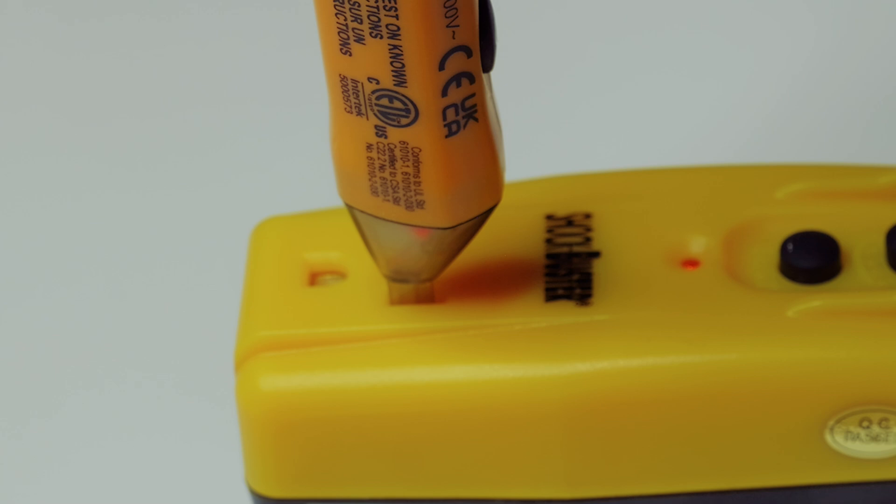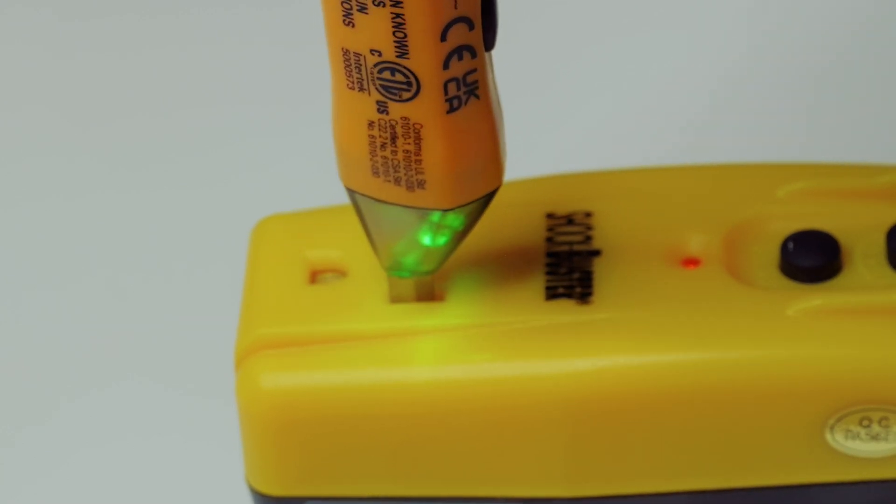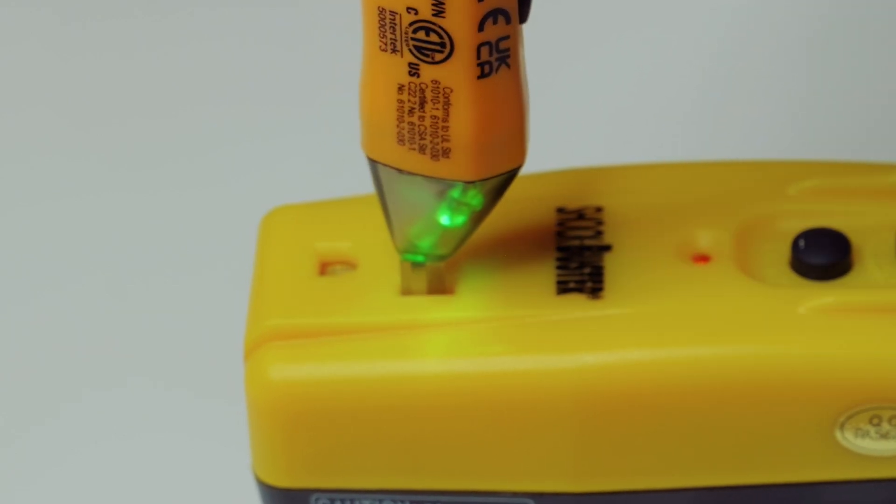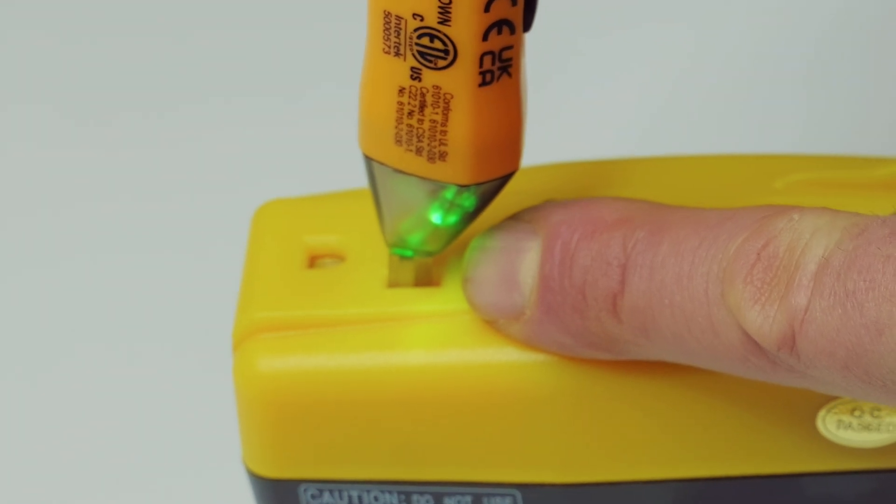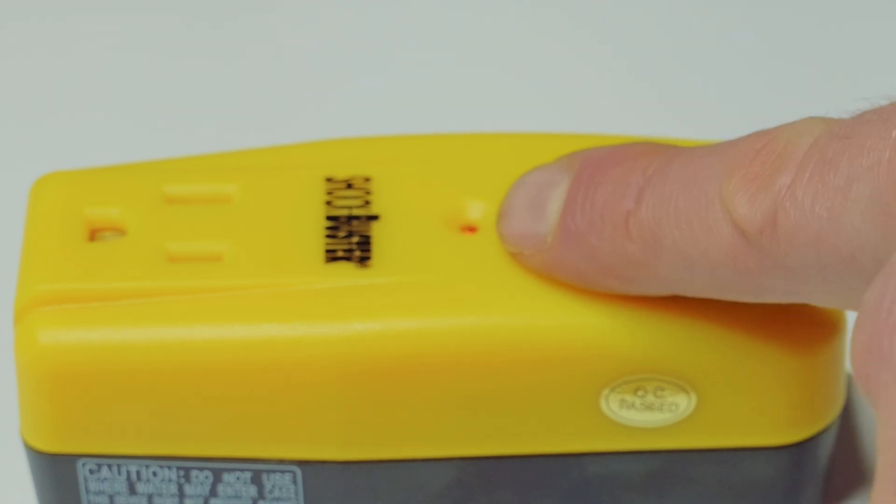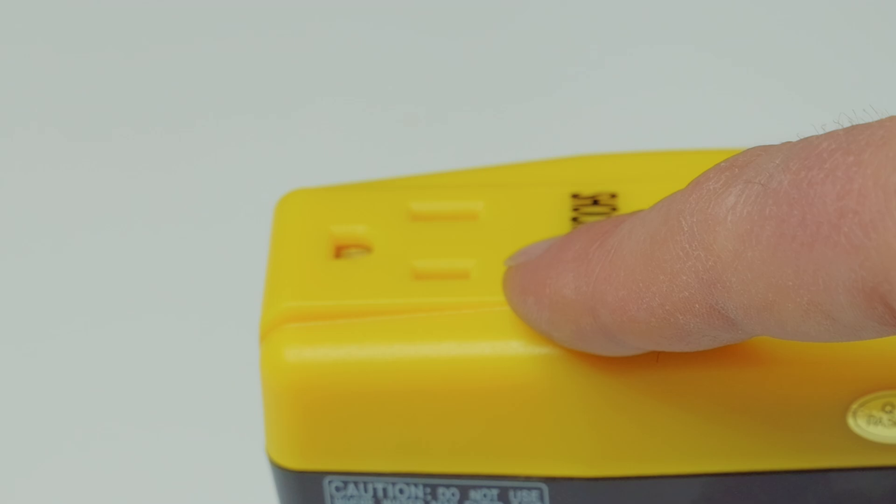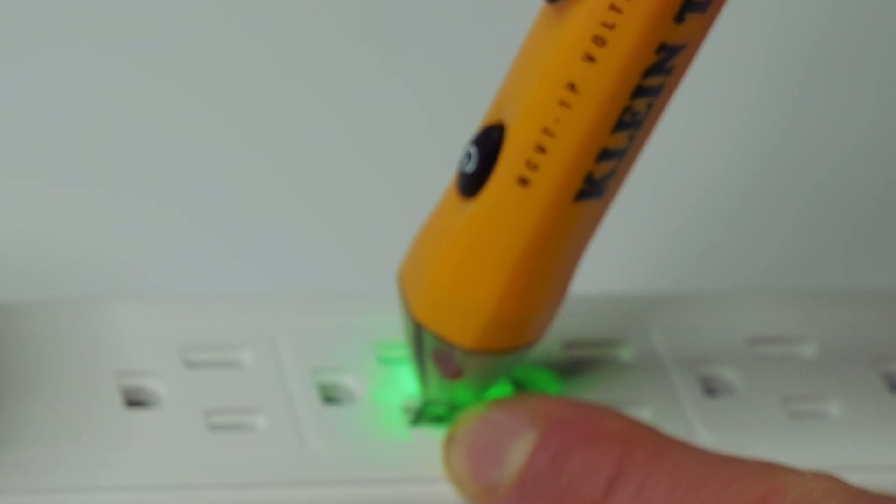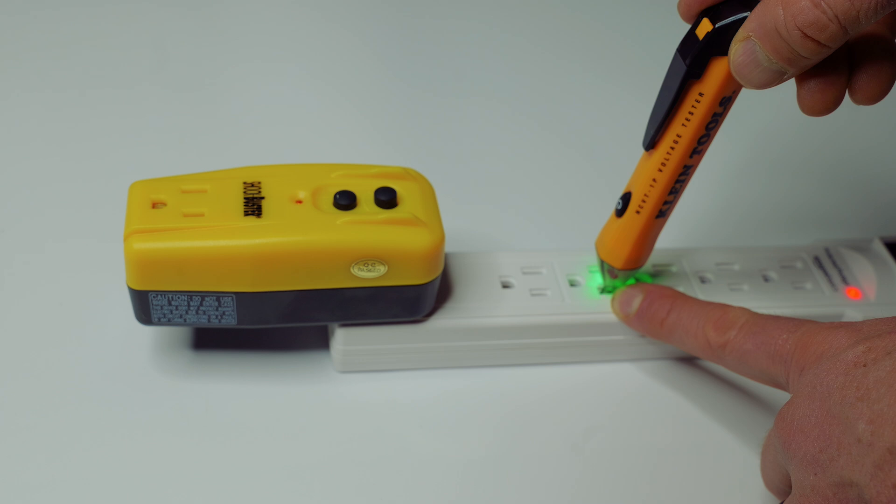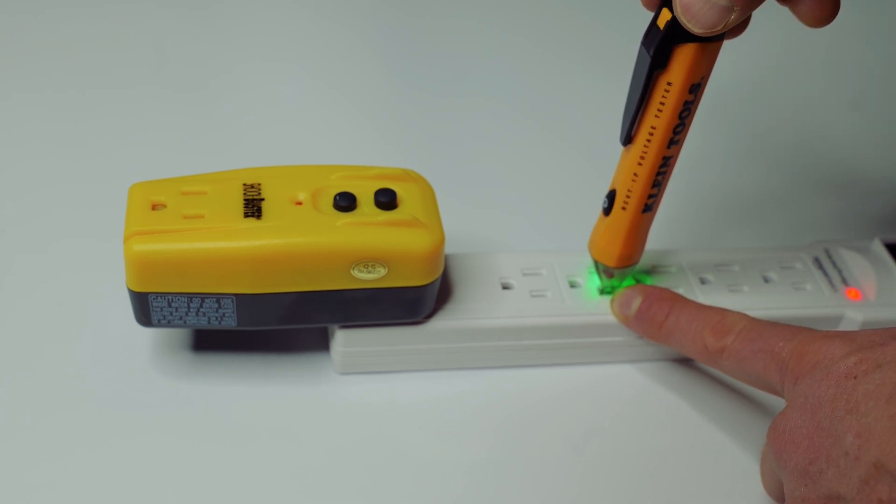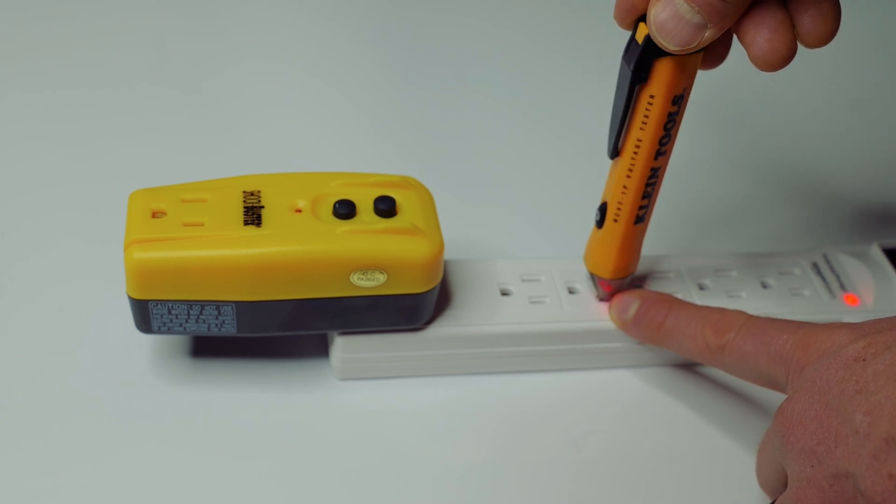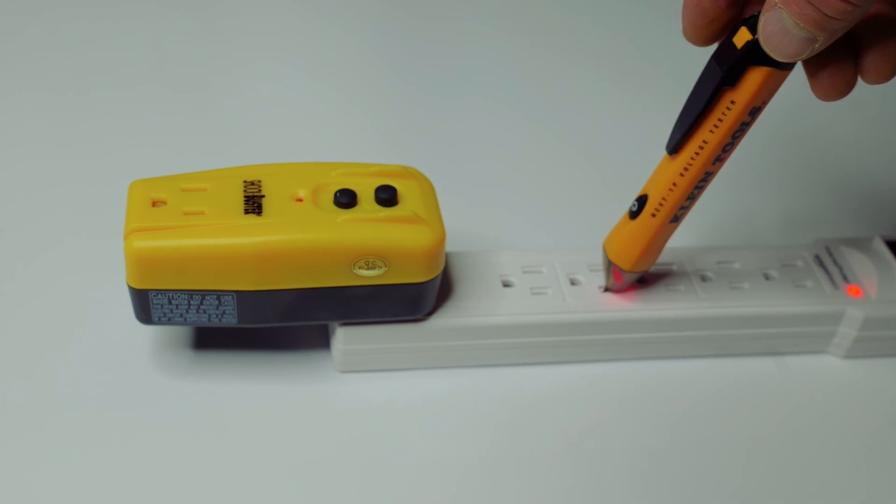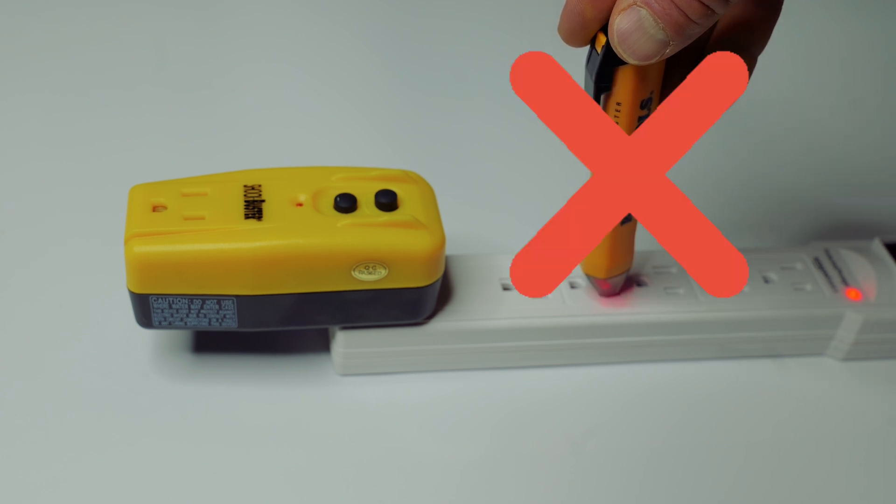Now I have not put a lot of pressure onto the voltage tester. If I were to put pressure down and push it in I can get it to flash red and green there. It's kind of going back and forth but I really got to push this in and that right there is a perfect example of how you can get a reading that tells you that you have removed power and the circuit is safe to work on. But folks, by this red LED here I can tell you that there is 120 volts AC on this. Okay now we'll move the Klein over to the regular power strip. Now that's on the neutral side. This is the hot side and I can push it down in it and it's red indicating that there is power on this circuit. But as you can see it just slightly pulled out and I've got green again. So this could be a false indication that you have removed power and the circuit is safe to work on. So be careful with this Klein tools. You really got to push it in and make sure you get a good connection. Get near that powered contact before it shows that red light. So to me the Klein tools NCVT 1P is not going to be a highly accurate non-contact voltage tester.